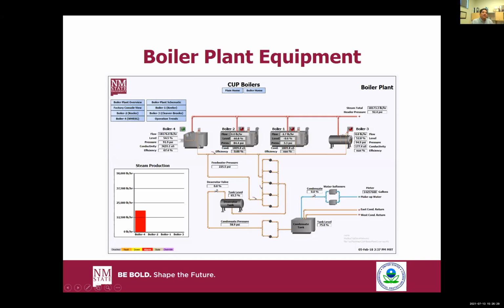That conductivity reading is really important—it tells you the hardness of the water. We've all seen what happens when you boil water out of a pan, or evaporate water—it leaves hardness or scale behind. So when we're running a steam boiler, we do have that hardness, and once it gets too mineralized, we have no choice but to remove that water from the system and run it into the drain. Of course, that's an undesirable loss of water, but it's just part of an industrial process that does exist.